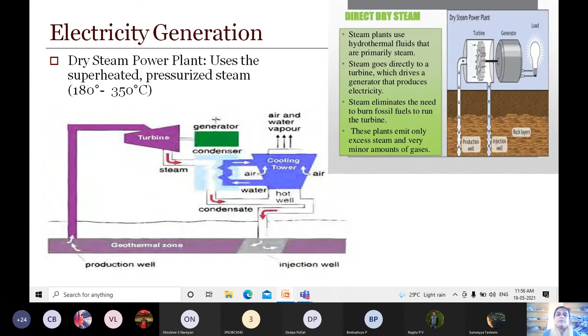Here they are saying that steam produced directly from the reservoir runs the turbine that powers the generator. The dry steam system is simple, and it requires steam and condensate injection piping. You can observe the steam and condensate injection piping here.